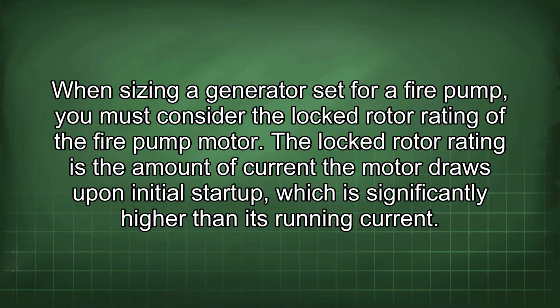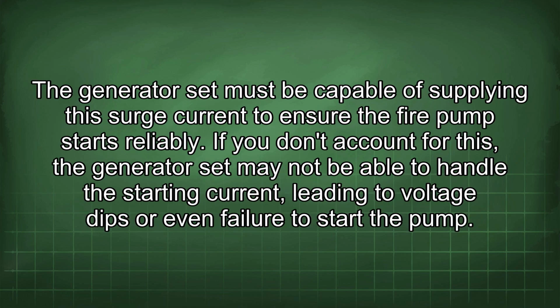When sizing a generator set for a fire pump, you must consider the locked rotor rating of the fire pump motor. The locked rotor rating is the amount of current the motor draws upon initial startup, which is significantly higher than its running current. The generator set must be capable of supplying this surge current to ensure the fire pump starts reliably. If you don't account for this, the generator set may not be able to handle the starting current, leading to voltage dips or even failure to start the pump.